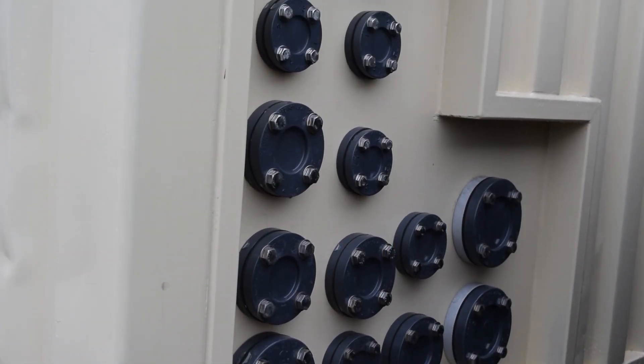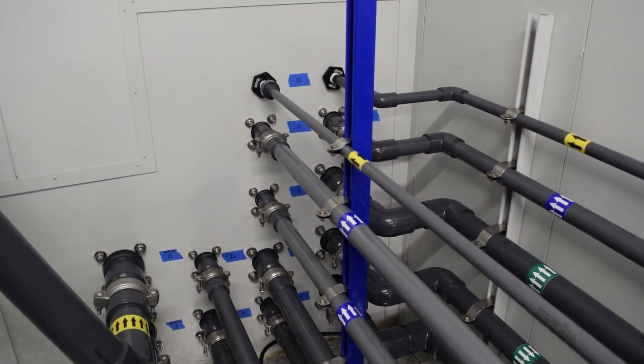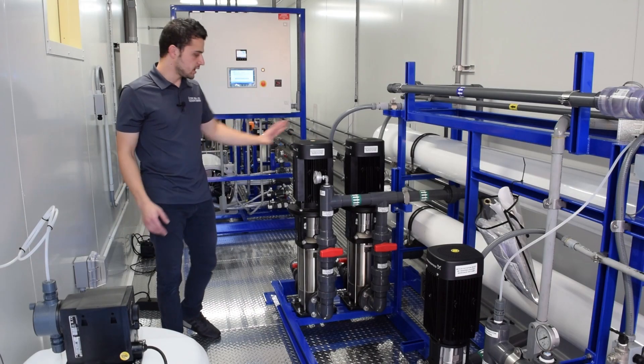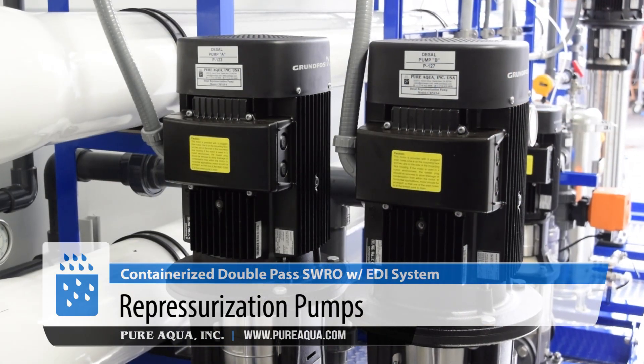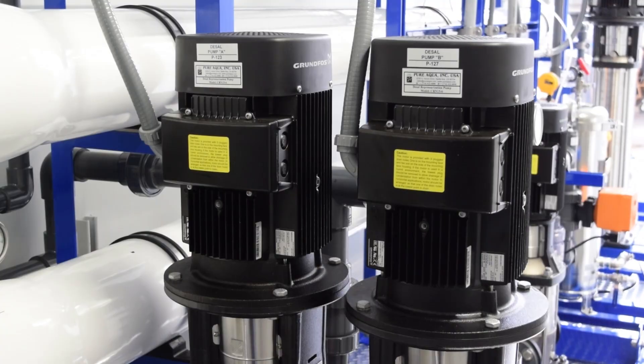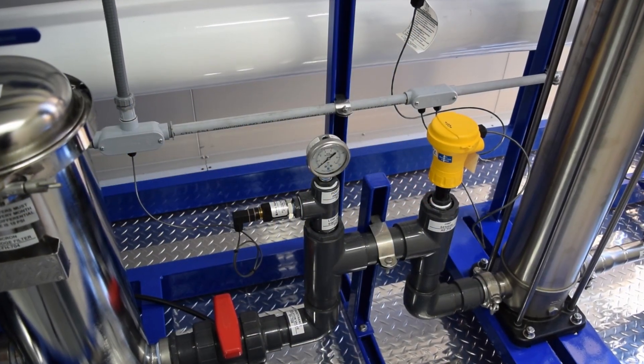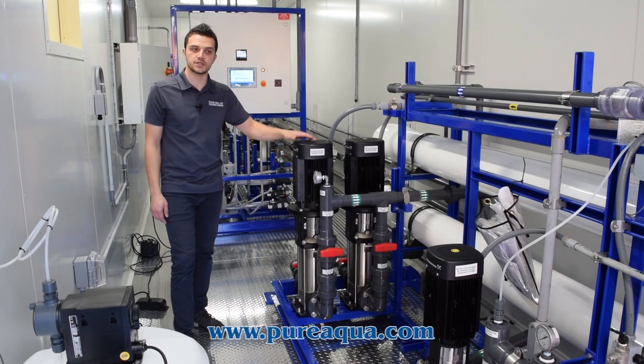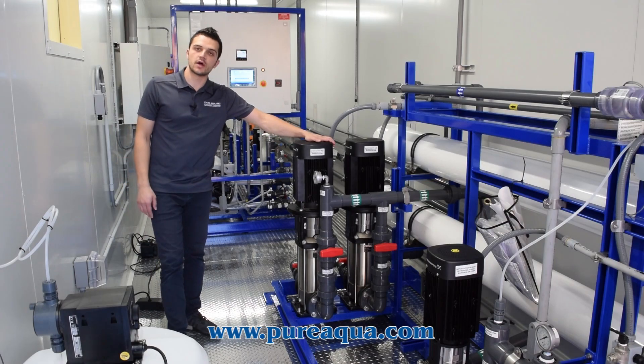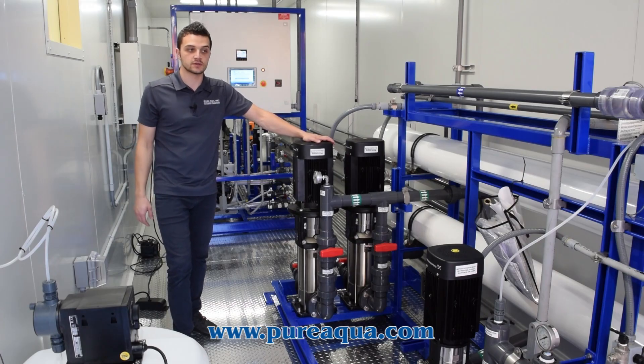As discussed in the previous container, part of the SWRO permeate gets repressurized for potable use, and the other part is fed into this container. These are the repressurization pumps for the desalinated water for potable use — a very straightforward setup with inlet and outlet isolation valves, pressure gauge, and a digital flow meter downstream to monitor the flow rate. These pumps alternate in operation and pressurize the water to around 100 PSI, because the final location on site is very far from where these containers are housed.